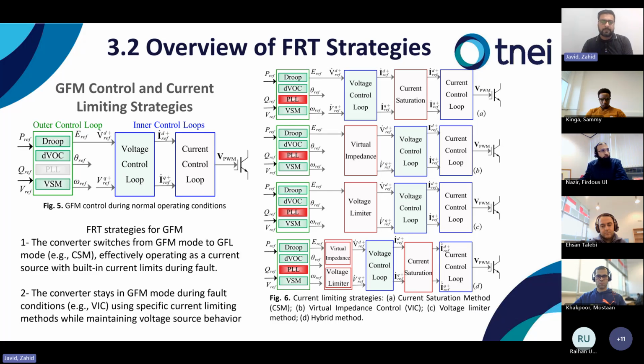The control strategy implies a hierarchical signal flow where the E reference from the outer control loop establishes a VD positive reference. Meanwhile, the VQ reference is kept at 0 to maintain proper alignment with the grid voltage reference frame. The voltage control loop processes these voltage references to generate corresponding current set points ID and IQ for the GFM terminals. These current references are then fed into the current control loop, which ultimately produces the PWM voltage modulation signal at the inverter terminal.